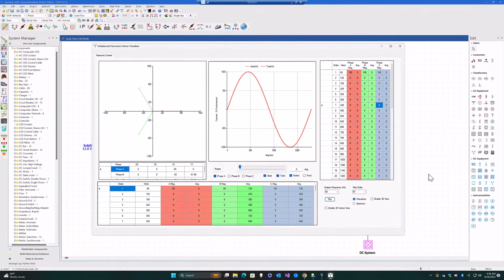So let's visualize our harmonics through the Unbalanced Harmonics Vector Visualizer, which is new in 2023. What we're looking at is a perfect sine wave on my chart on the right hand side, and on the left hand side, we can see the vectors, which are perfectly balanced and 120 degrees apart from each other for phase A, B, and C. And just for simplicity, I'm showing you phase A for the waveform only. We can turn on phase B and C later on. And in terms of the harmonics, we have only the fundamental current. So of course we see a perfect sinusoidal wave.